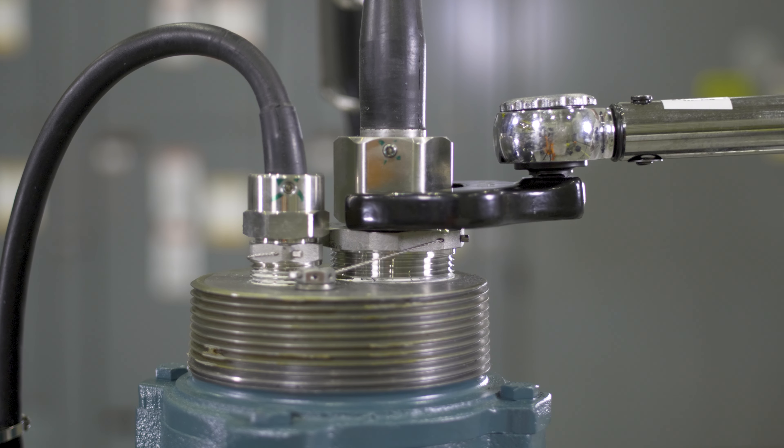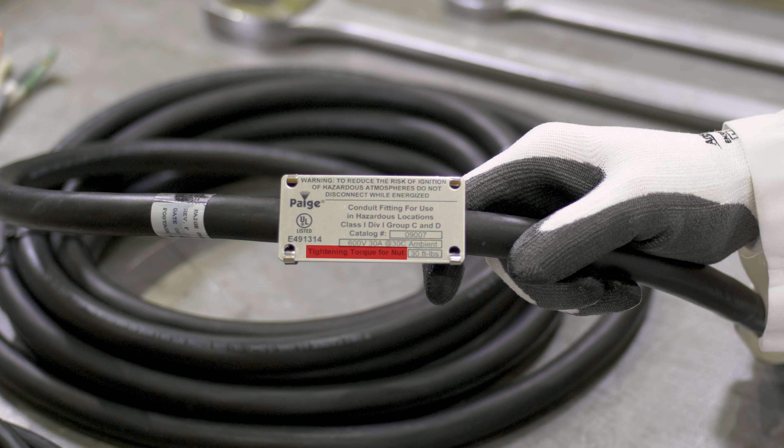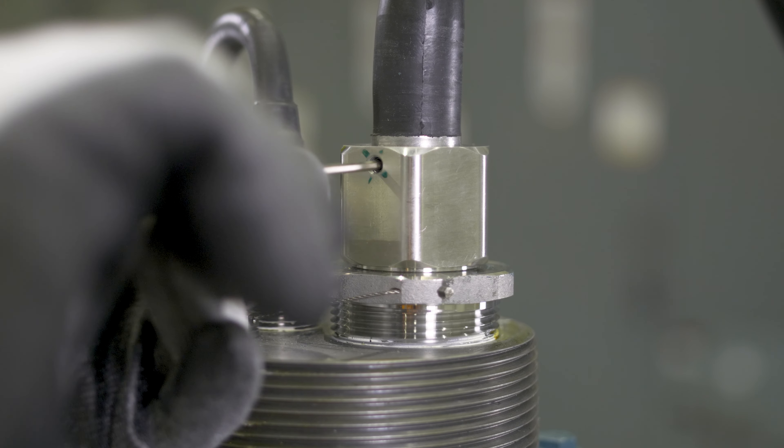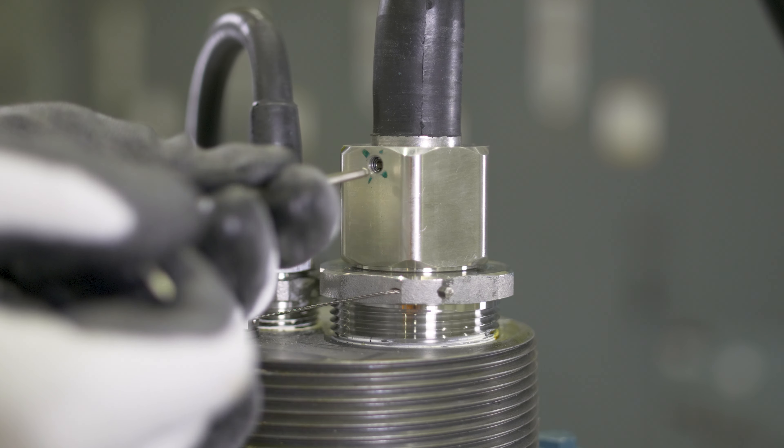The proper tightening torque will be displayed on the tag attached to the cable. Once the nut is properly tightened and the metal sleeve on the cable is extended through the nut, tighten the set screw into the sleeve to prevent the nut from loosening.